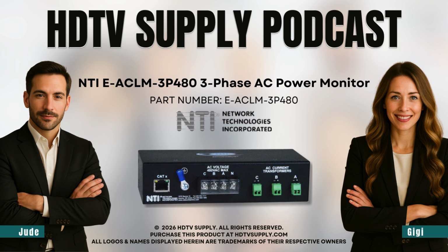Exactly. And that brings up the most critical point. Safety. First, you need what are called current transformers, or CTs. Think of them as sensors. They let the monitor safely measure huge currents without being wired directly into a lethal amount of voltage. And those are sold separately, I saw. They are. And second, and this is the big one, the voltage inputs connect directly to the live line. So this has to be installed by a qualified electrician. Right. And the main electrical service for the building must be shut down first.